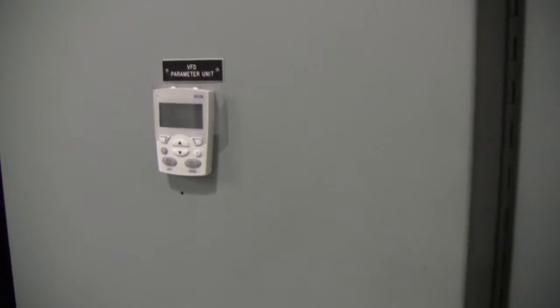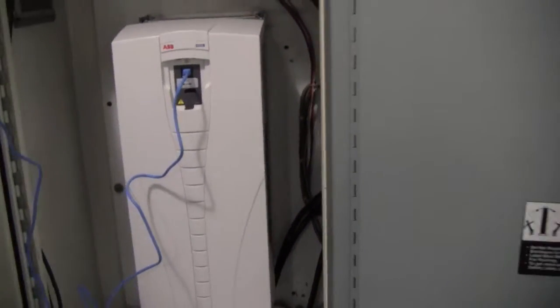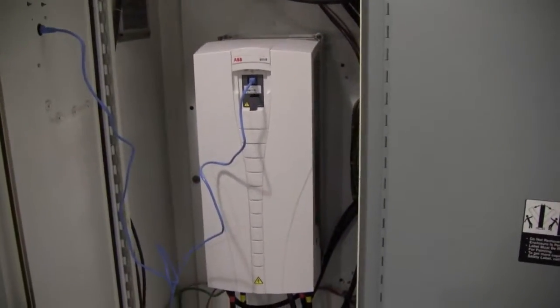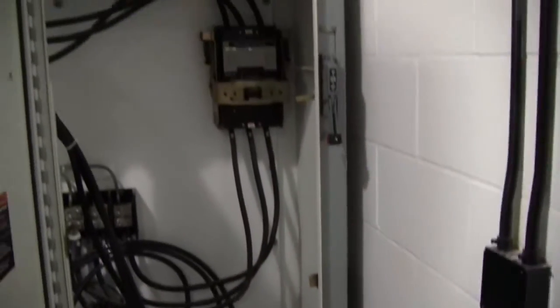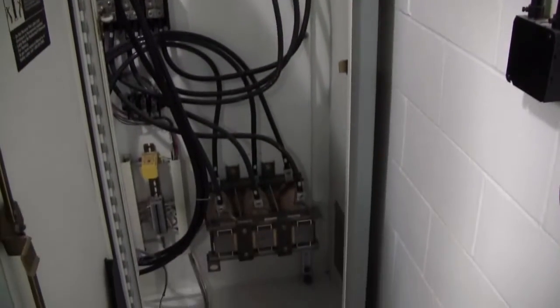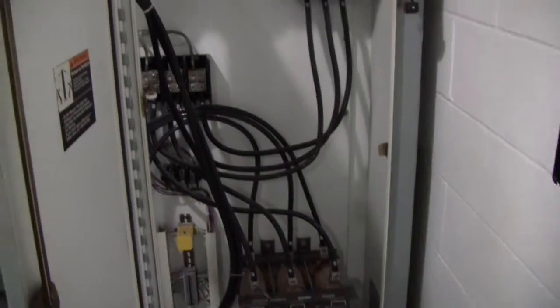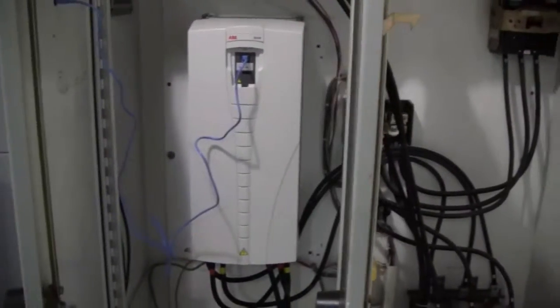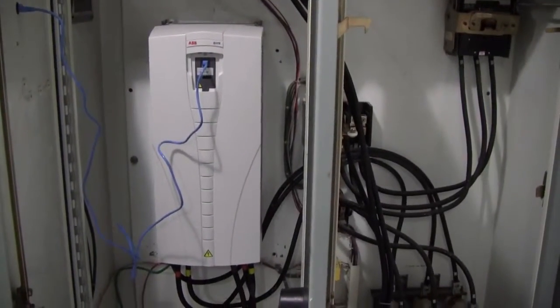So we ended up retrofitting a new ABB right there. I thought that was pretty cool. Able to get it in there, saved all the original casing, circuit breaker, input line reactor, and so on. And then the drive just slipped right inside. 150 horsepower, 460 volt.